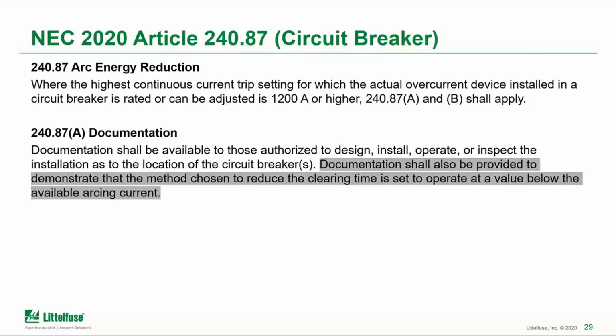240.87 has a requirement that's been in here for a few code cycles to have arc energy reduction whenever you have a circuit breaker that can be adjusted to 1200 amps or higher. And it's interesting to note it's not when it's set, but if it just can be set to 1200 amps or higher.